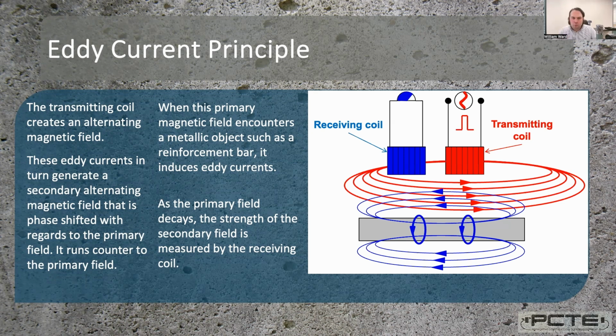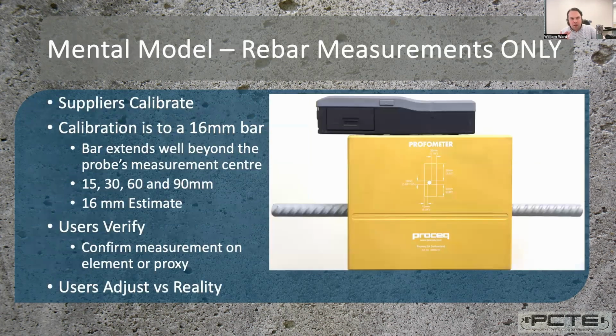So the best way to use a cover meter and to use it accurately and with confidence is to have a mental model of what we use it for and the particular things that will affect the measurement but cannot themselves be measured. So I've got here an illustration of the actual calibration check block for a cover meter.